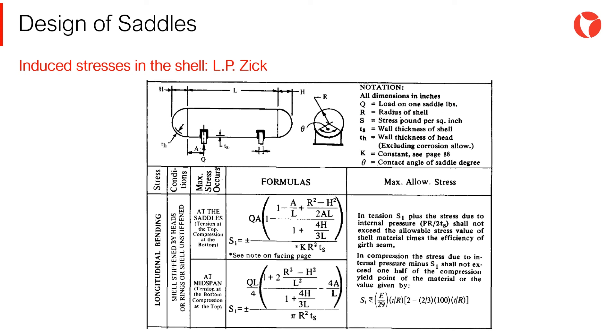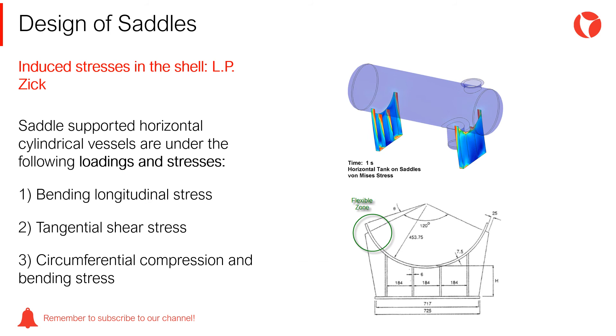One of the most important aspects of the design of saddles for horizontal vessels is the forces induced in the shell. To check the stress state of the shell, normally the Zick method is followed. The Zick work to determine stresses in the shell of pressure vessels gained such relevance that it was adopted and published by the ASME Code for Pressure Vessels. A methodology for the determination of stresses in the shell and heads of a horizontal pressure vessel supported on saddles was first published in 1951 by L.P. Zick.